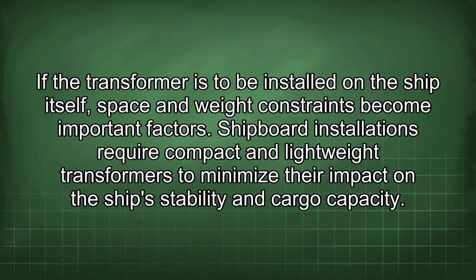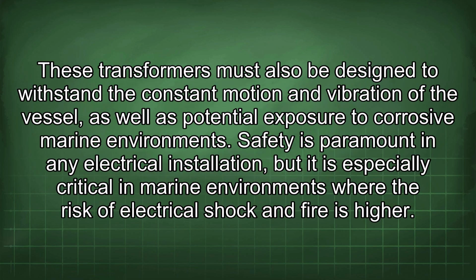If the transformer is to be installed on the ship itself, space and weight constraints become important factors. Shipboard installations require compact and lightweight transformers to minimize their impact on the ship's stability and cargo capacity. These transformers must also be designed to withstand the constant motion and vibration of the vessel, as well as potential exposure to corrosive marine environments.